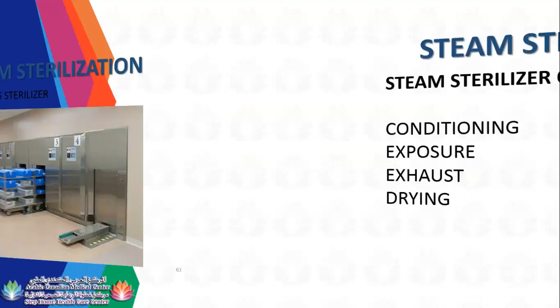So for your steam sterilizer cycles, it will start with conditioning, exposure, exhaust, and drying. For drying, actually, this is optional. There are times the machine has no drying, but the important three are conditioning, exposure, and exhaust. The drying is optional, but it is necessary because it can facilitate the drying of your instruments. Okay. Some machines don't have the drying, but the conditioning, exposure, and exhaust are present.